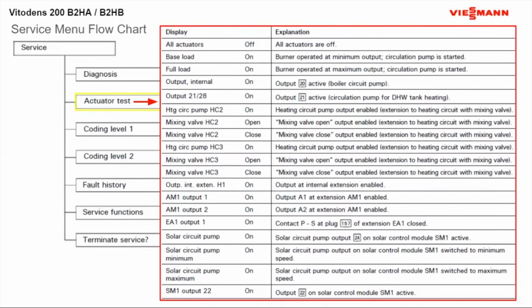So if you want to check that 20 pump output, remember that's your pump output that's going underneath your boiler, pumping into your boiler. Each time you hit the down arrow and it comes up to that 20 pump output, you click OK on that, and then you can go down to the relay, that 20 pump output where you tied your 20 pumps, and see if there's power there. If there's power there, then we know that there's something wrong with maybe our circulator, could be jammed or could have died out. So it's just a nice, easy troubleshooting thing.